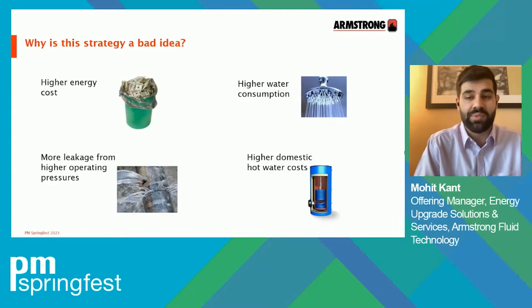So what's the solution? Presenting the design envelope booster. Each design envelope booster uses vertical multi-stage pumps in a 2 to 5 pump arrangement, combined with variable speed controls and efficiency-based pump staging logic to create broad envelopes of efficient hydraulic performance. The design envelope approach to selection reduces design risk due to set envelope and maximizes high-efficiency operation. The selected booster system can also accommodate changes during the design and construction phases and over the life of the building, wherein pumps can be added and removed as necessary.